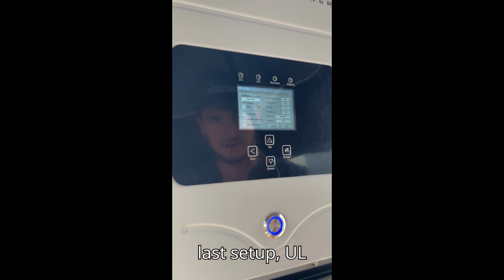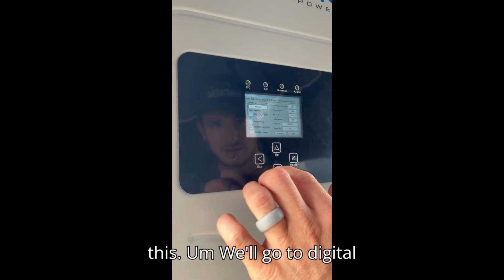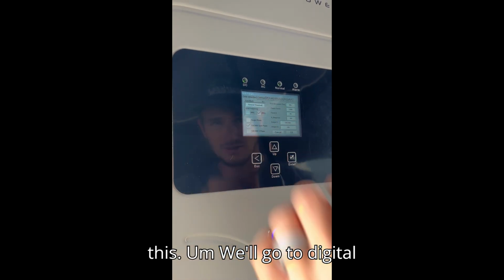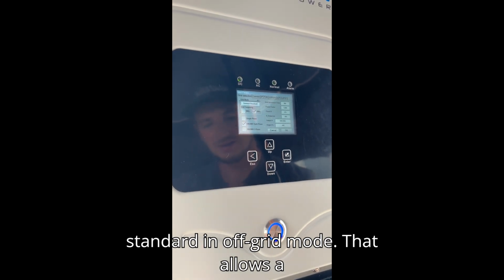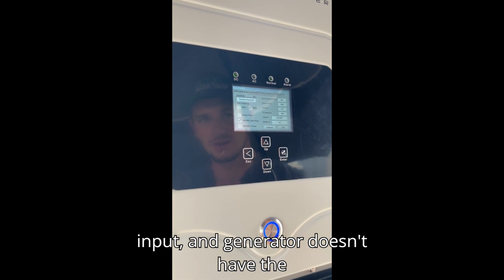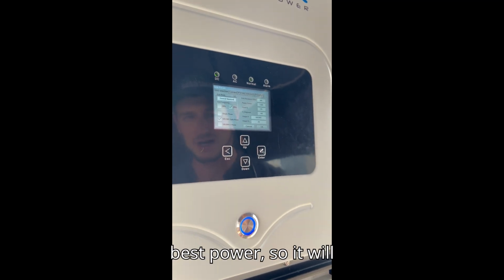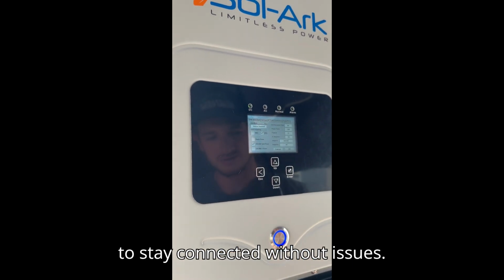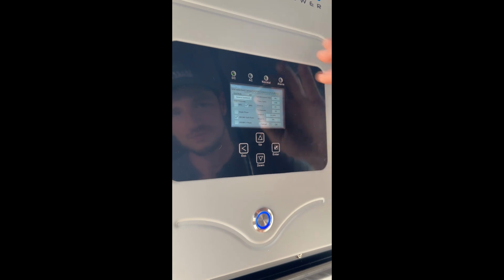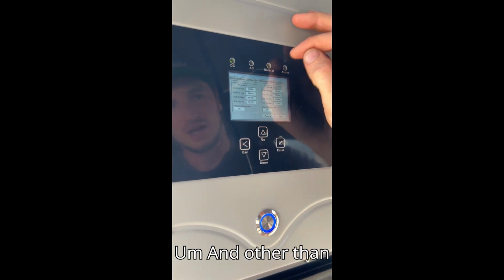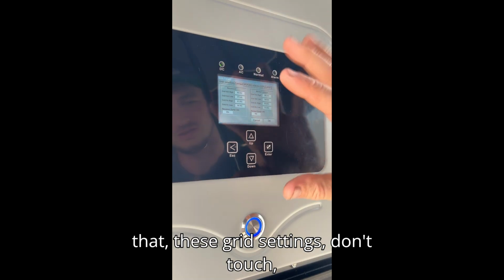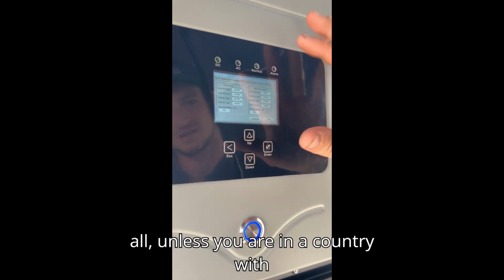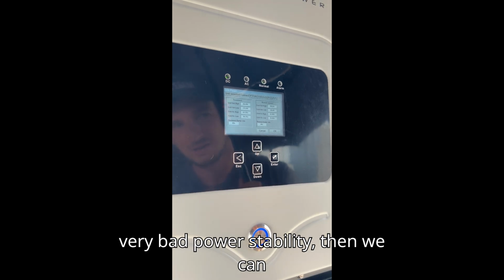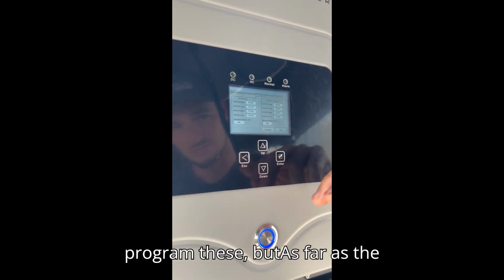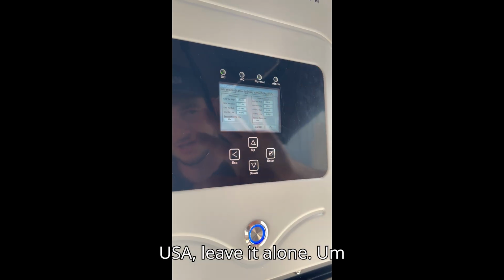Okay, our last setup, UL. We'll go to general standard and off-grid mode. That allows a generator to be connected to the grid input, and since a generator doesn't have the best power, it will have a better tolerance for a generator to stay connected without issues. Other than that, these grid settings we don't mess with at all unless you are in a country with very bad power stability, then we can program these. But as far as the USA, leave it alone.